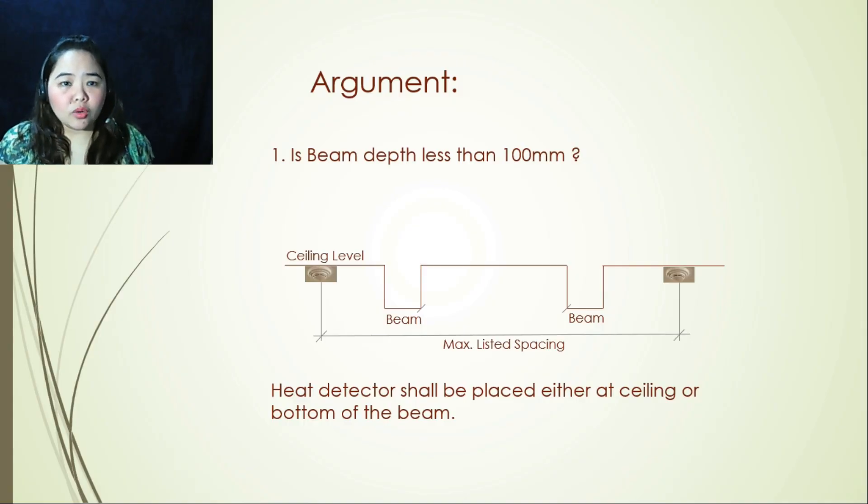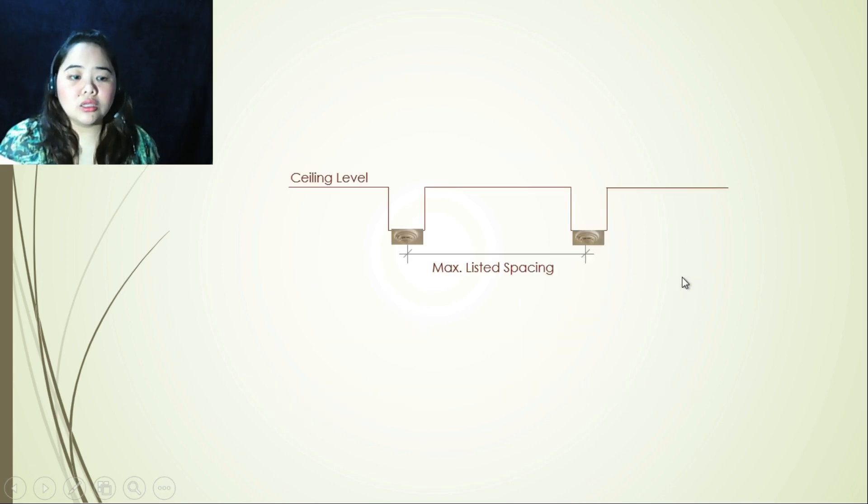So now that we know the rules, we proceed with the arguments. Argument number one is beam depth less than 100 millimeters. If so, that will be considered a smooth ceiling, so you will then follow the maximum listed spacing. So again, if you were to follow NFPA standards, that's 15 meters, but you can also refer to your manufacturer. Heat detector shall be placed either at ceiling or bottom of the beam. So here is our ceiling, you can place it either here or onto the bottom of the beam, still following maximum listed spacing.